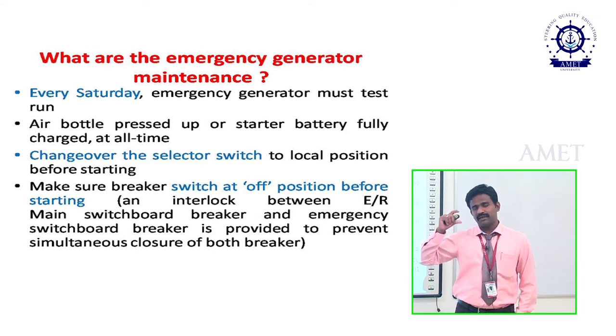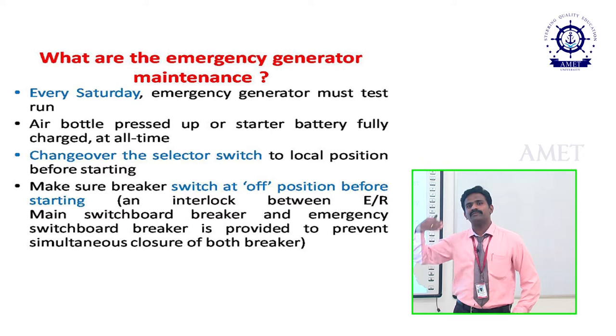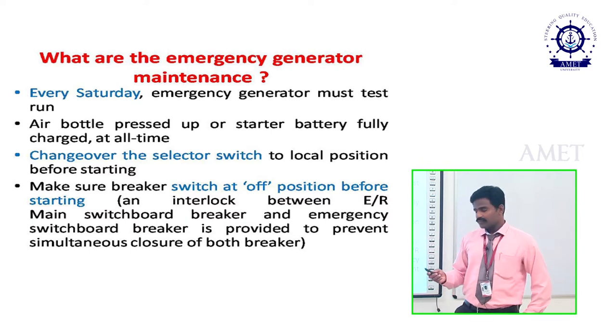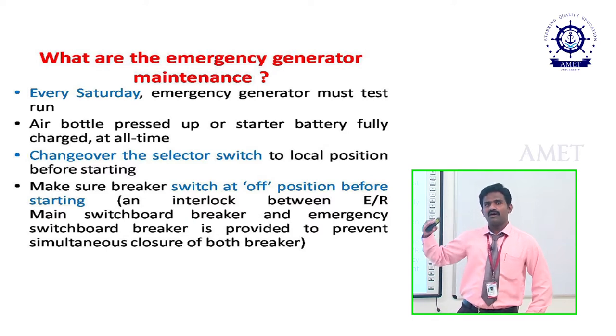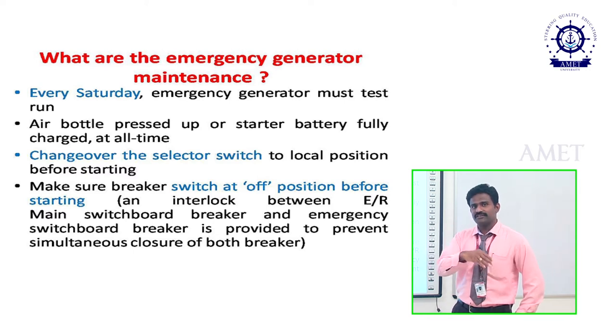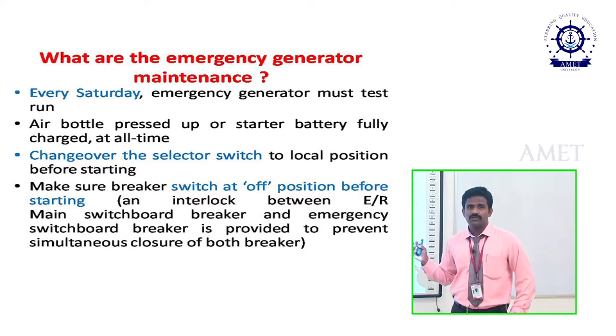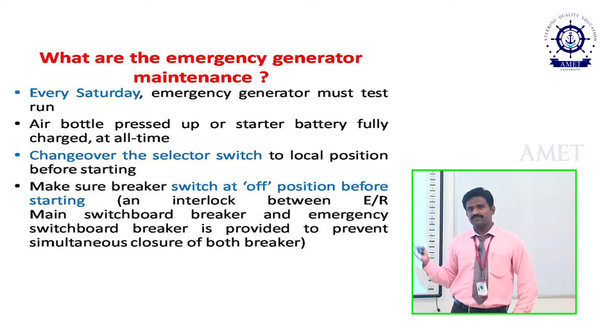There is a connection between the main switchboard and the emergency switchboard. In normal condition, the power supply to the emergency switchboard comes from the main switchboard. During an accidental condition, the main switchboard turns off and power to the emergency switchboard comes from the emergency generator. On that occasion, the switch from the main side will be off and the emergency generator switch will be on. This on-off situation is controlled by the changeover switch.